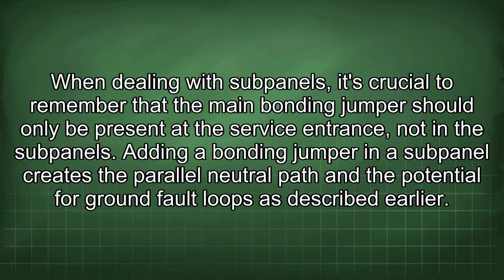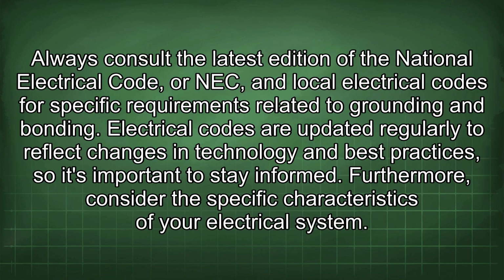Adding a bonding jumper in a subpanel creates a parallel neutral path and the potential for ground fault loops as described earlier. Always consult the latest edition of the National Electrical Code, or NEC, and local electrical codes for specific requirements related to grounding and bonding. Electrical codes are updated regularly to reflect changes in technology and best practices, so it's important to stay informed.